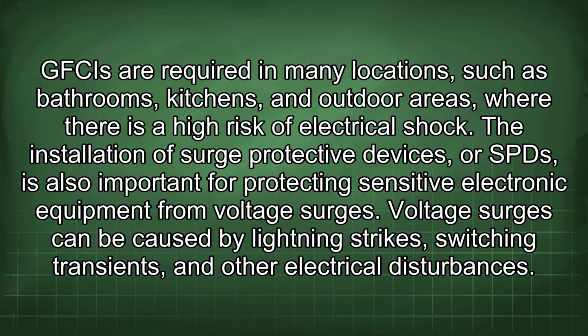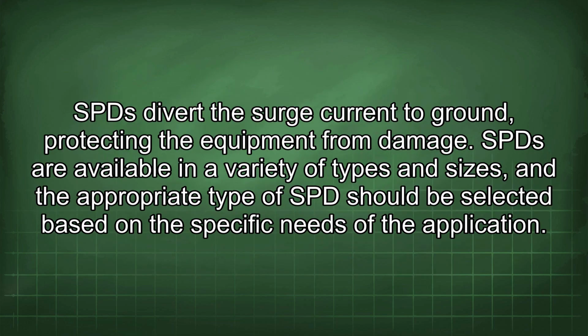Installation of surge protective devices, or SPDs, is also important for protecting sensitive electronic equipment from voltage surges. Voltage surges can be caused by lightning strikes, switching transients, and other electrical disturbances. SPDs divert the surge current to ground, protecting the equipment from damage. SPDs are available in a variety of types and sizes, and the appropriate type of SPD should be selected based on the specific needs of the application.